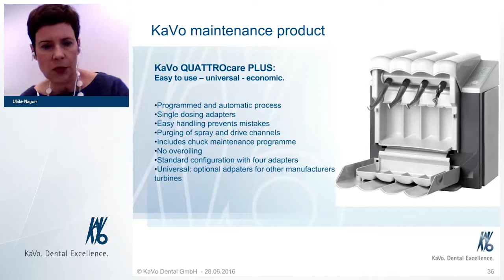What is essential here is that the whole lubrication process happens fully automatically. That means we avoid any over-oiling or under-oiling of the instruments, and automatically during the oiling process we have a so-called purging of the spray channels and the drive channels, again to avoid over-oiling. The big benefit of all automatic devices is, of course, that you avoid handling mistakes. Many of you might know the KaVo spray. It's a very reliable product in maintenance.